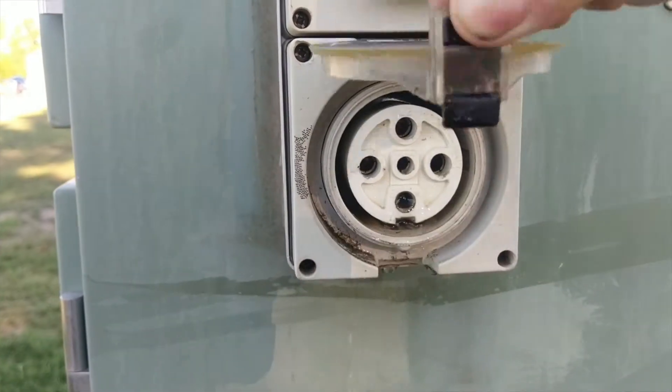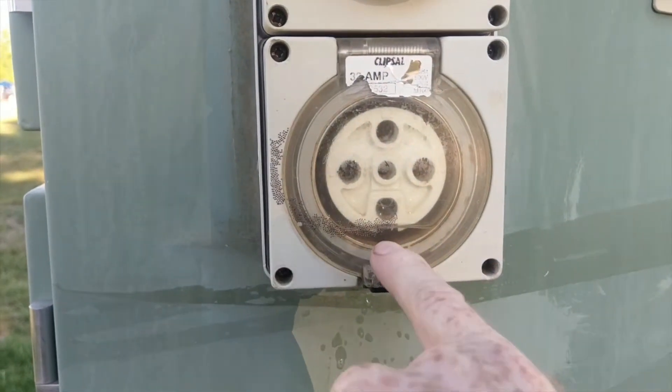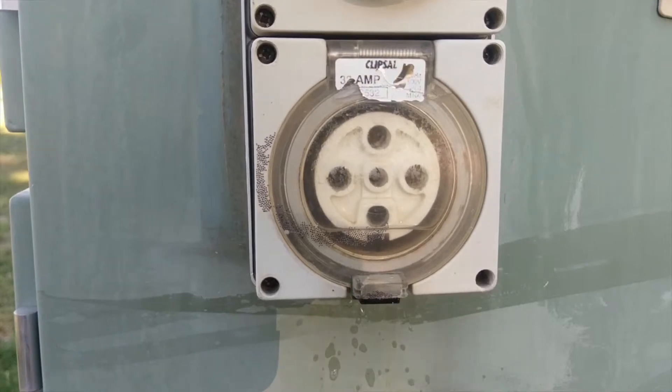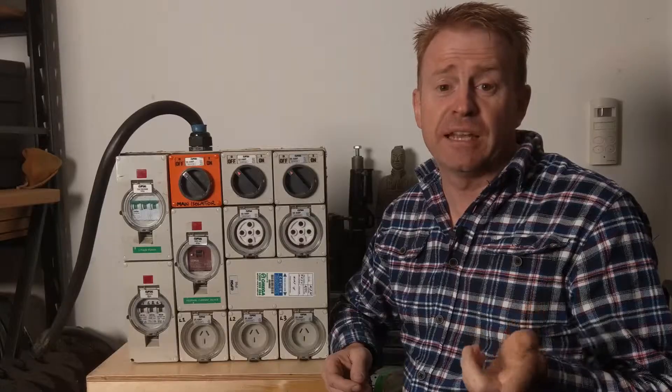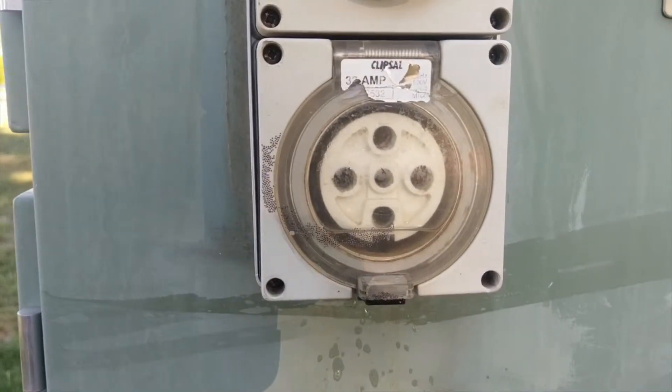At least 12 times in the 20 years that I've been a gaffer I've come across this scenario where a power outlet is full of water. Now the interesting thing to note with this outlet is when I close it it fills with water again.